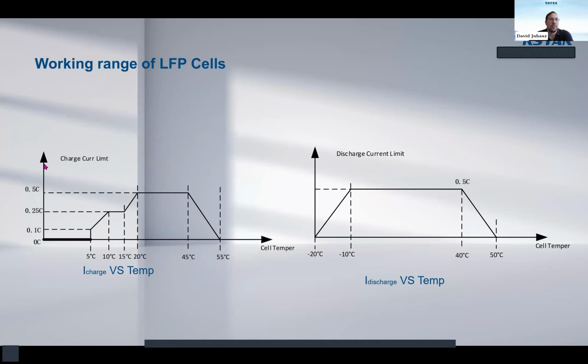Regarding the characteristics of the lithium iron phosphate cells, the charge and discharge rate is 0.5 C. So that means, if we have a 50 kilowatt discharge or charge rate of this system, and we have 100 kilowatt hour storage capacity, if we divide it together, we get this 0.5 C. And the charge and discharge power is degraded when it reaches 45 Celsius. And for the discharging, it's limiting the current at 40 Celsius.